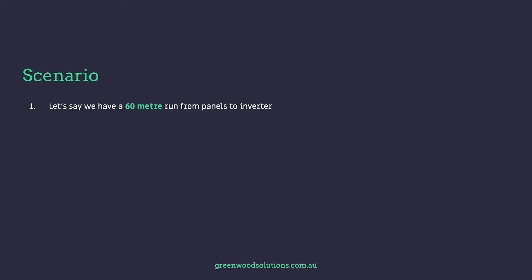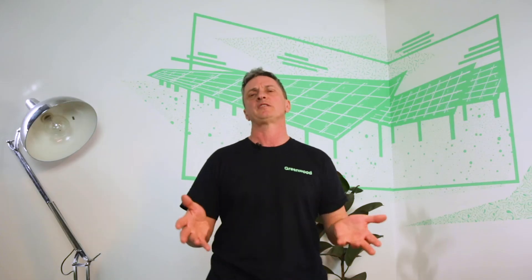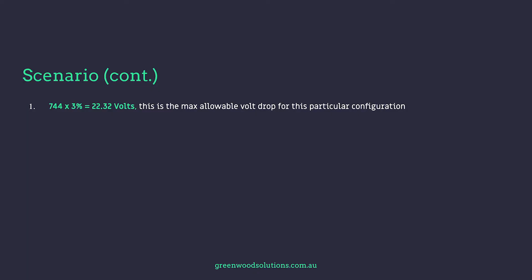Let's say we have a 60-metre run from panels to the inverter and we're using 19 panels in series. The total voltage at maximum power point of those 19 panels in series is 744 volts, and we have a 3% allowance on the Volt Drop. So how many volts have we got to play with? You take 744 volts at maximum power point, multiply by 3%, and it comes out to around 22 volts.